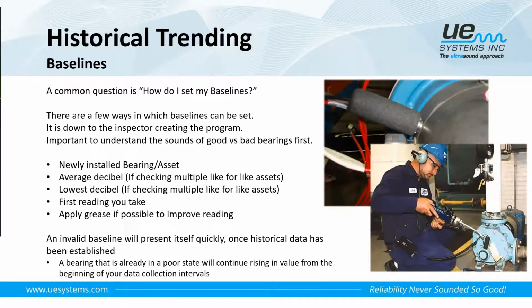The thing about baselines is that if you have an invalid baseline, or one that's in a degraded state, for example, it will quickly present itself to you. Once you start collecting historical data, you will see the decibel value begin to rise over time. And it will continue to rise because it's already in a degraded state. So even if you do make a mistake with a baseline, you will highlight this as you collect more data.